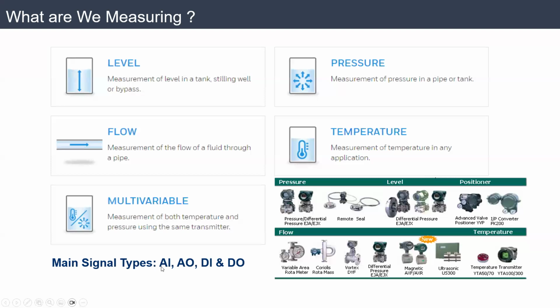Analog input means I am reading values, but they are numbers. For example, level is an analog input - I'm reading level, for example 50% level in the tank, that's analog input. Or I am reading pressure, or I'm reading temperature - for example the temperature inside the tank is 70 degrees Celsius. So this is AI. If I am sending to the tank, for example I need the temperature inside the tank to be 70%, so I am sending AO. So if I am sending from the control room to the plant, we'll call it output. If I am receiving from the plant to the control room, I'll call it input.